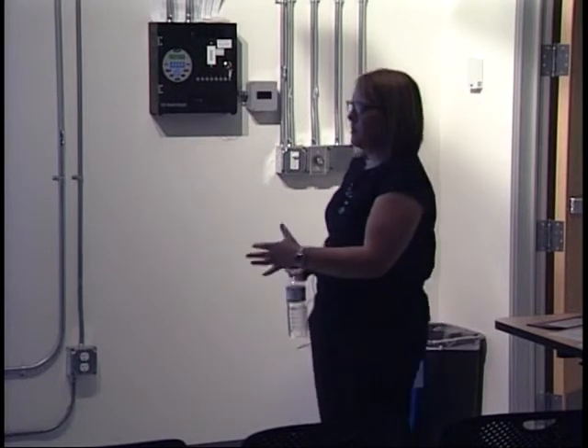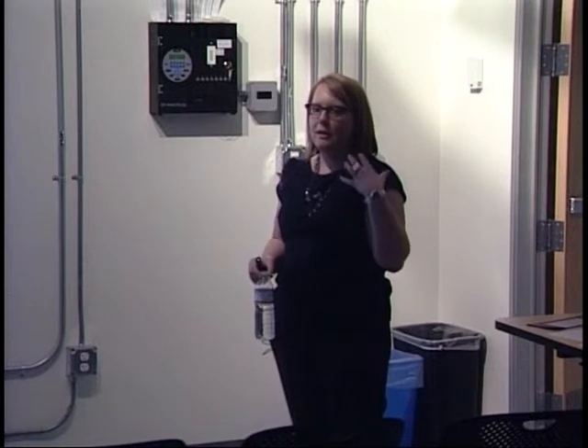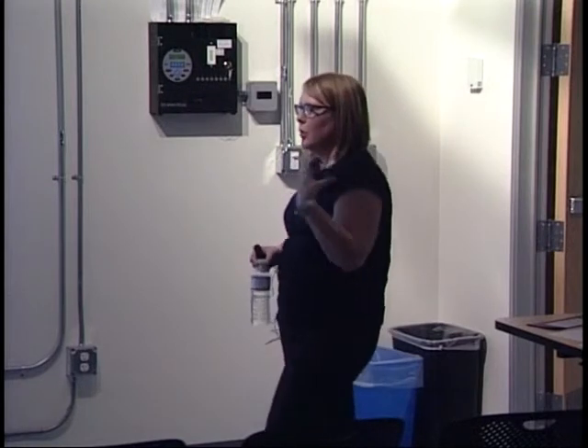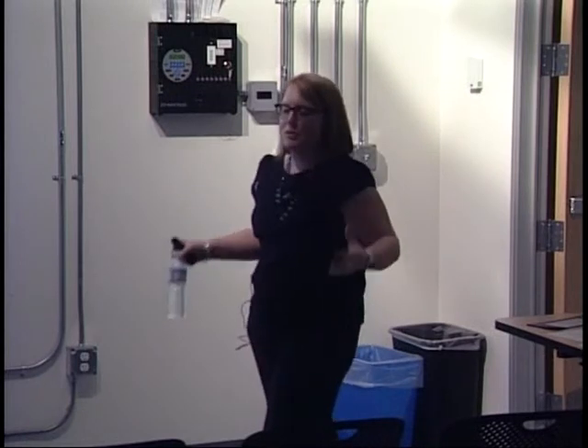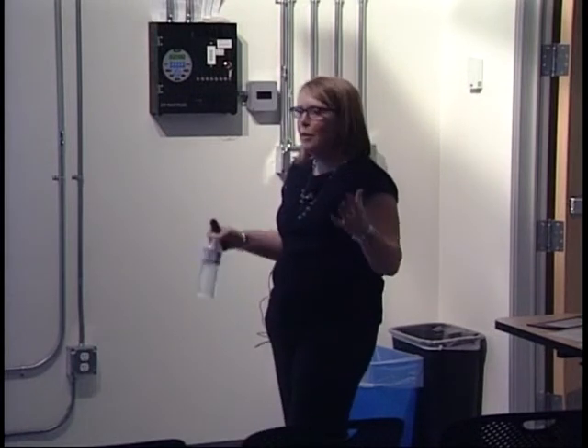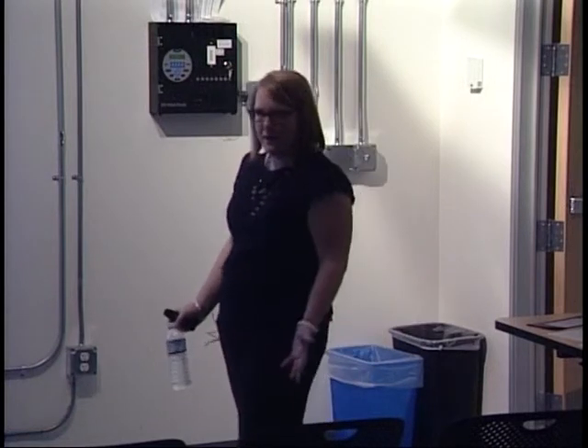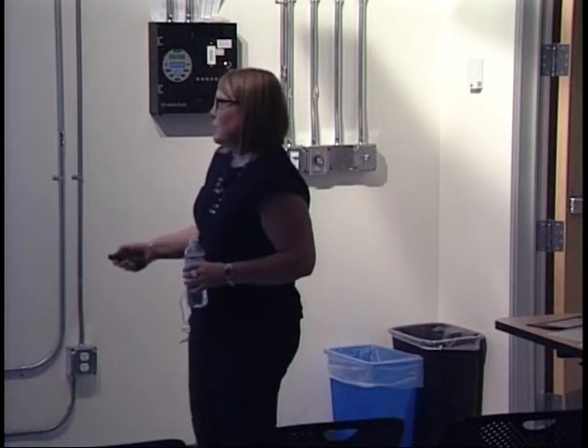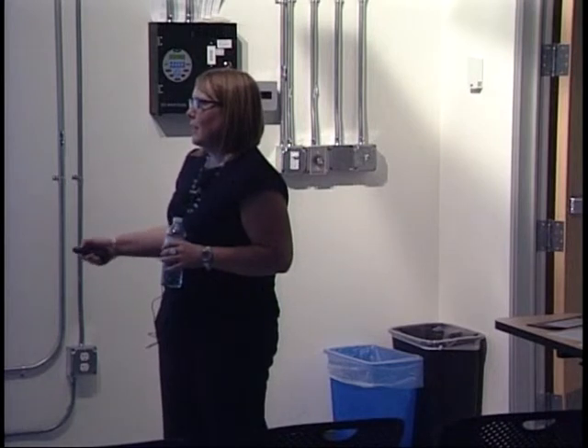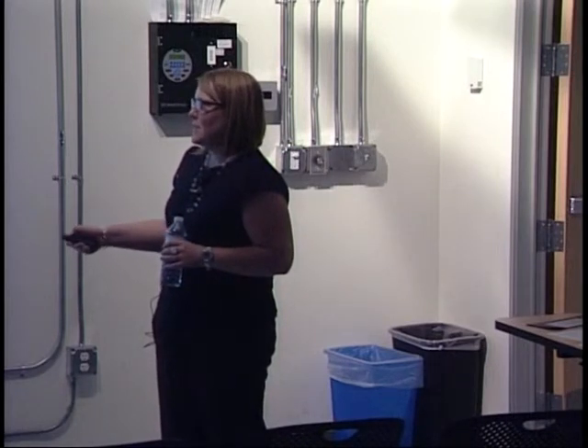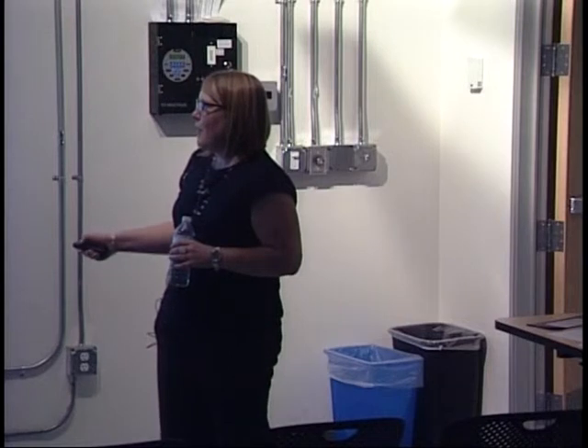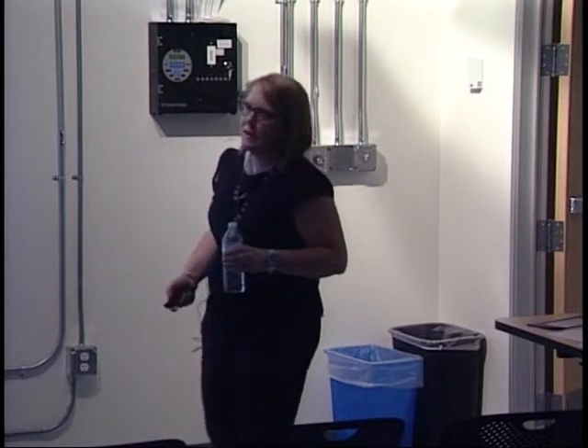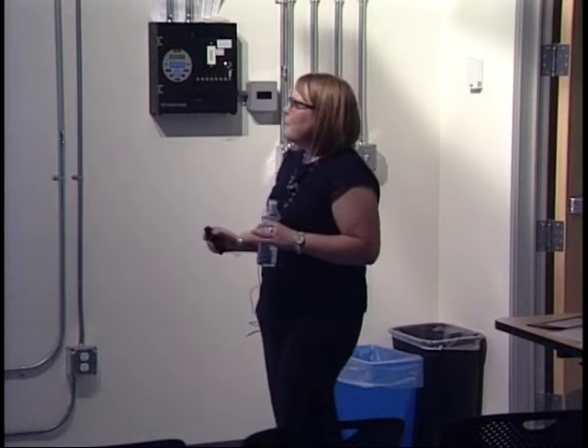We know hospitals are an internally dominated load issue - what I mean is the ventilation air is what drives the energy use. We can only go so low on the ventilation rates, they're code regulated. So that's what's driving the energy use, especially in the top part of this graph - it's still the air change rates driving that.